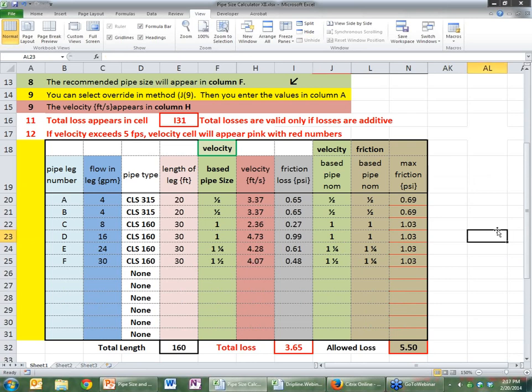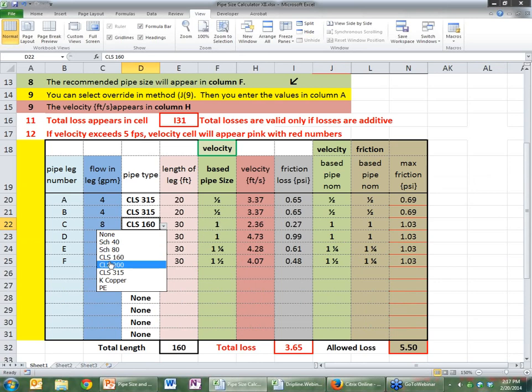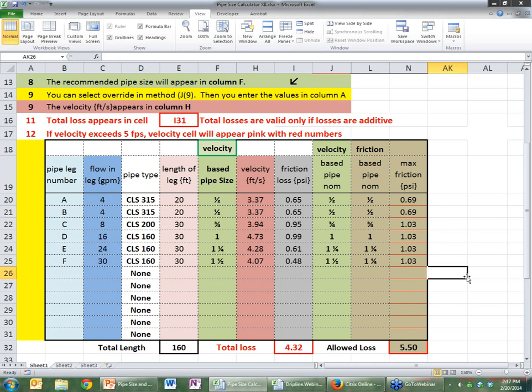Notice that the velocity square here in the pull-down menu is set light green. It's now light green in this column F. So that's what we're using as velocity. The pipe size chosen is one and a half now, and the velocity is below the 5 feet per second. Now, there's another thing I want to show you here, and that has to do with the pipe type. You might say, well, why did we choose to go to class 160 down here and 315 here? And let me show you another thing. Let's switch this to class 200. Right now, in 160, the pipe size selected is 1 inch. Let's go to 200. And it changes to 3 quarters.